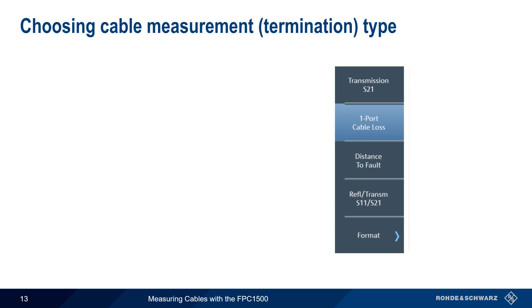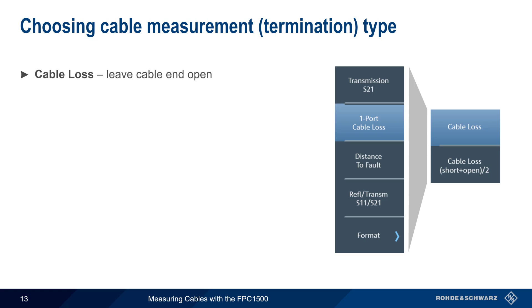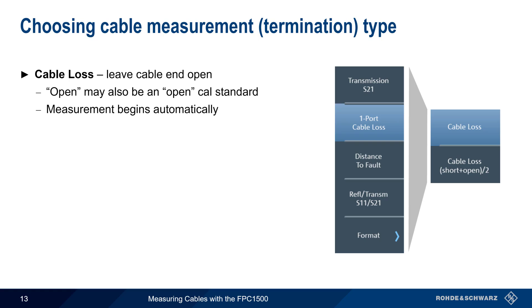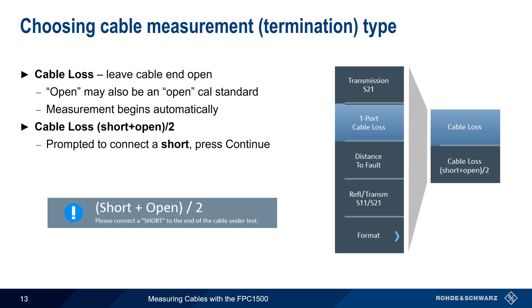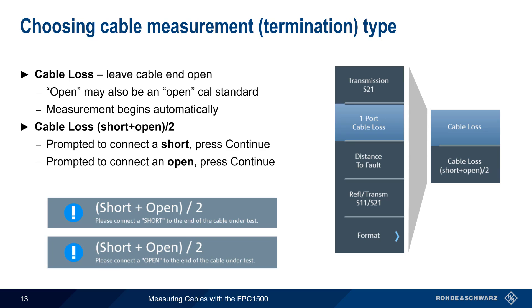The next step is choosing the cable measurement or termination type. If we choose Cable Loss, then the end of the cable should be left open or unterminated. Note that an open may also be created by attaching an open calibration standard. This type of cable loss measurement begins automatically. If we choose Cable Loss Short Plus Open Divided by 2, the cable will be measured twice – once with a short and once with an open. Attach a short when prompted and press Continue, and then leave the cable open or connect an open when prompted and press Continue again. After the process is completed, the results will be displayed.